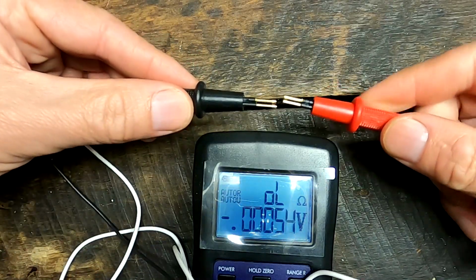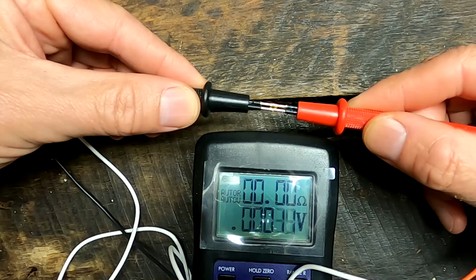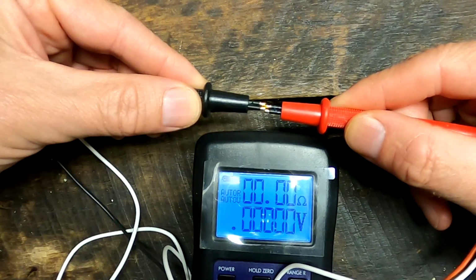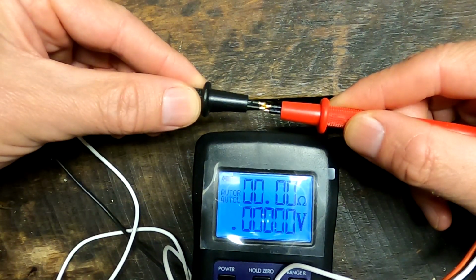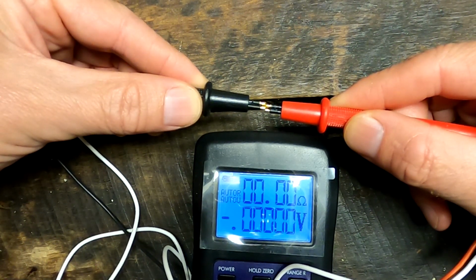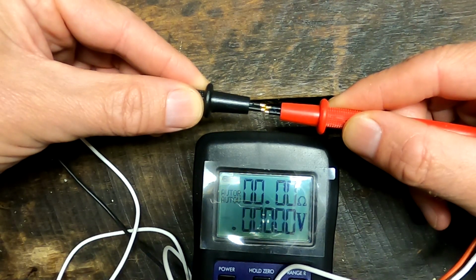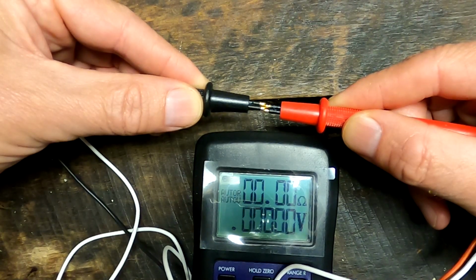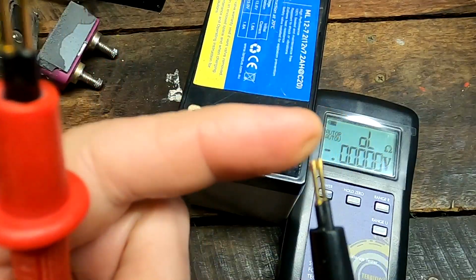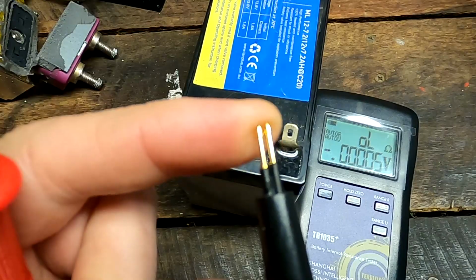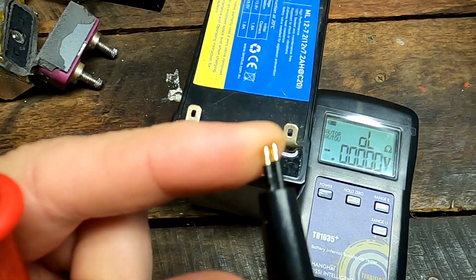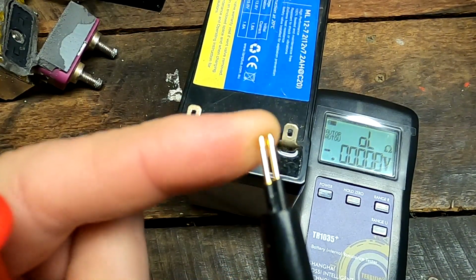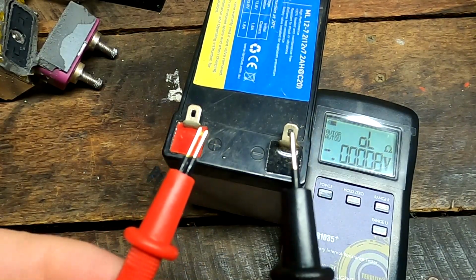So at the very first start, we short our probe cables here, and we can see we've got 0.00 ohms and all zeros for the volts as well. So this is pretty much calibrated now to compensate for the probe leads and cables. You can see the probe tips are spring loaded to apply a certain amount of pressure on the terminal to make the best contact possible.